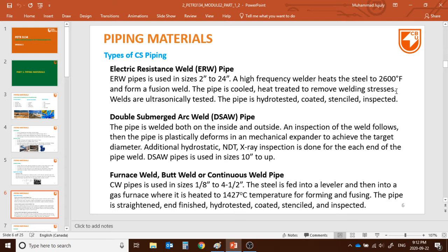Heat treatment removes the weld stress. If the welding stress is not removed, the pipeline becomes very susceptible to corrosion and can fail easily. After heat treatment, the welds are ultrasonically tested and the pipe is hydro-tested, coated, stenciled, and inspected.